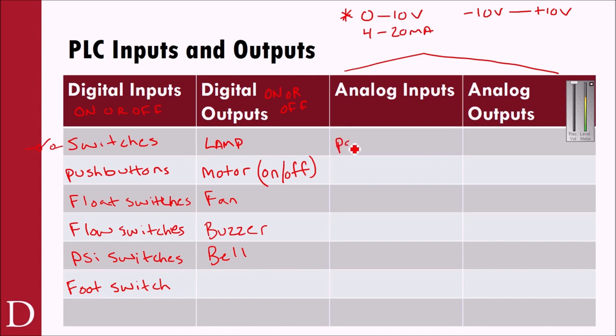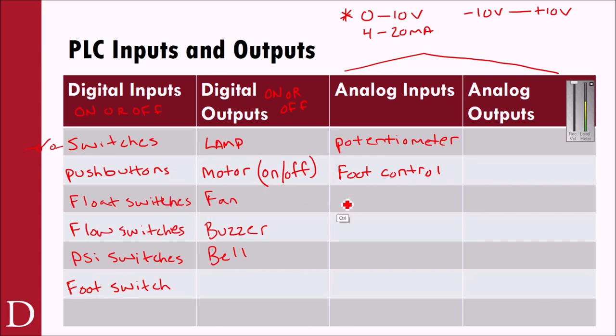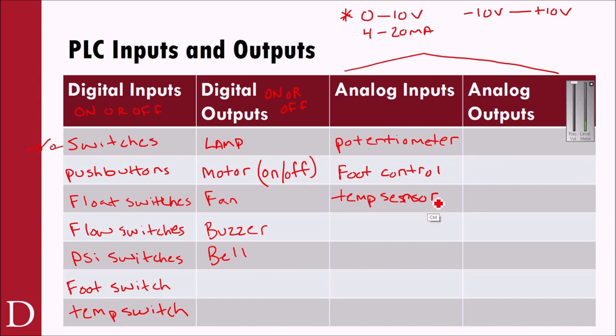An analog input could be something like a potentiometer — think of it like a dimmer switch in your living room where we control the lamp level, not just turning it on or off. Other analog inputs include a foot control that varies between 0 and 10 volts instead of just being on or off, and a temperature sensor. A temperature sensor reads 0 to 10 volts — so at 0 degrees Celsius you read 0 volts, and at 100 degrees Celsius you read 10 volts.